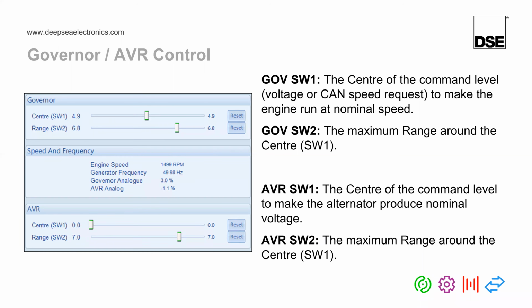So if you're ever wanting to calculate the maximum voltage drop you might see across a governor or AVR control cable using a DeepSea module, you could make the assumption that the maximum current coming out of the DeepSea module's output was 20 milliamps. Then, knowing the resistance of the cable that you have used, you can work out the voltage drop, because voltage drop is just current times resistance.